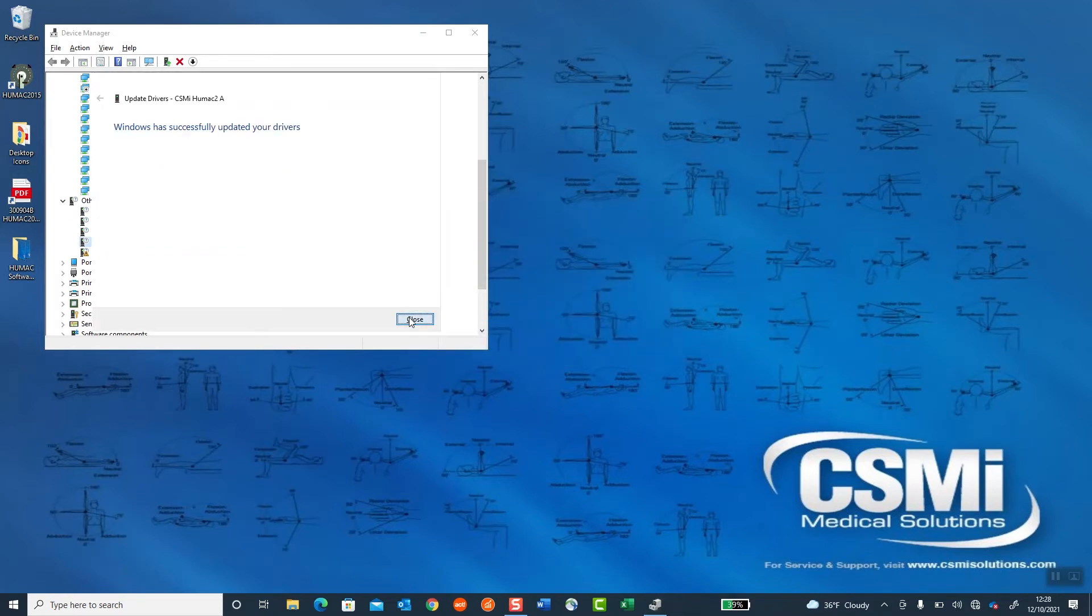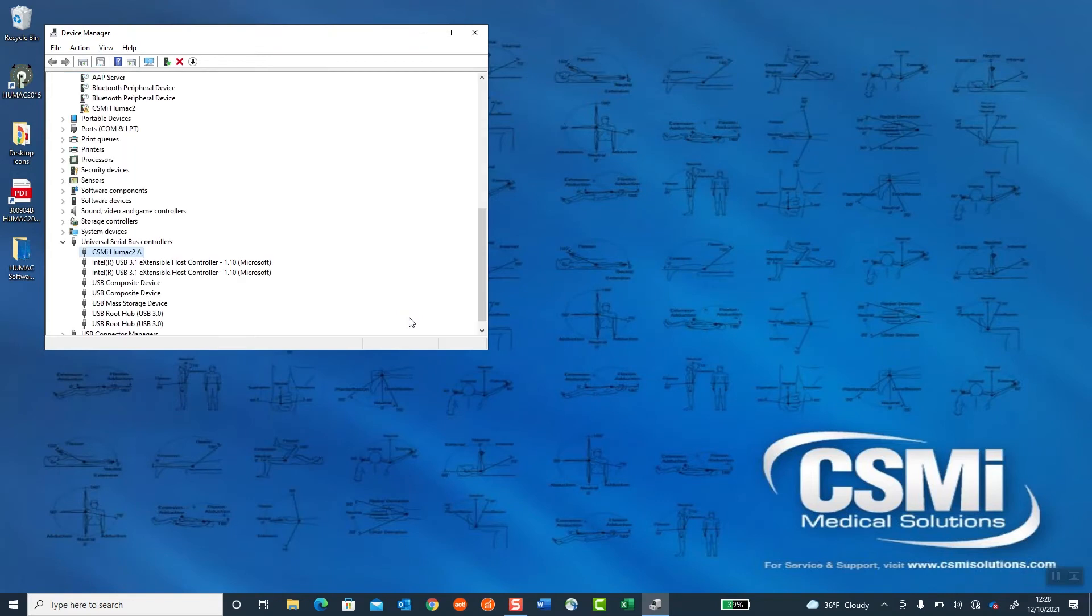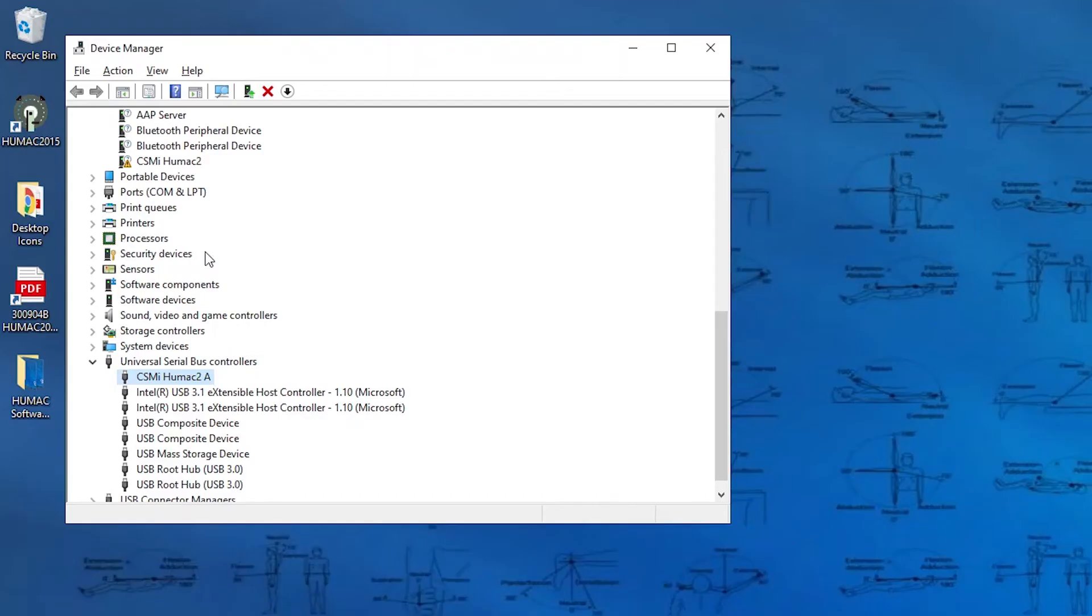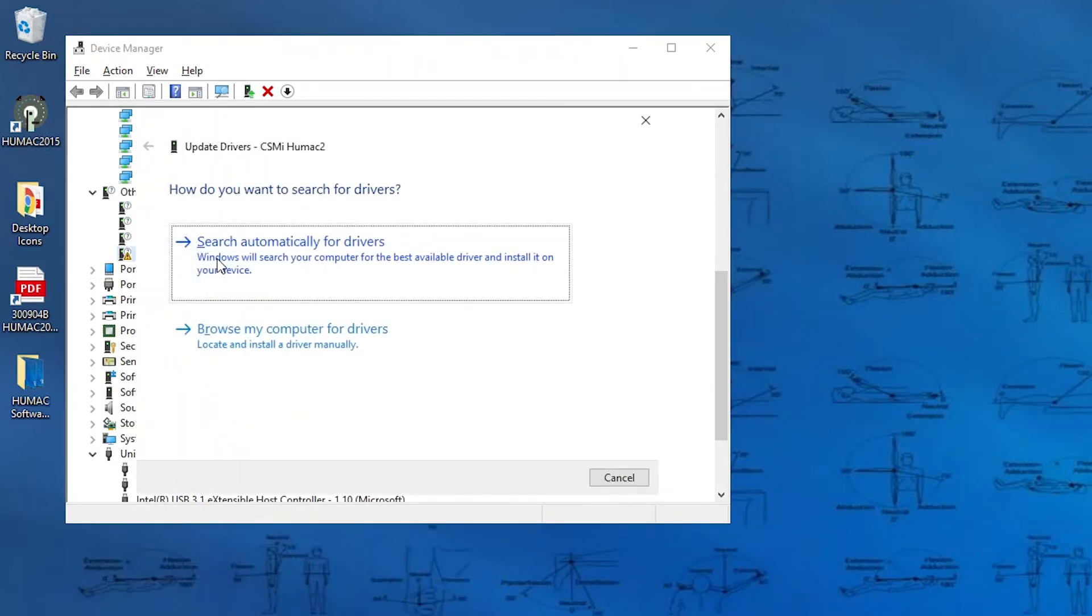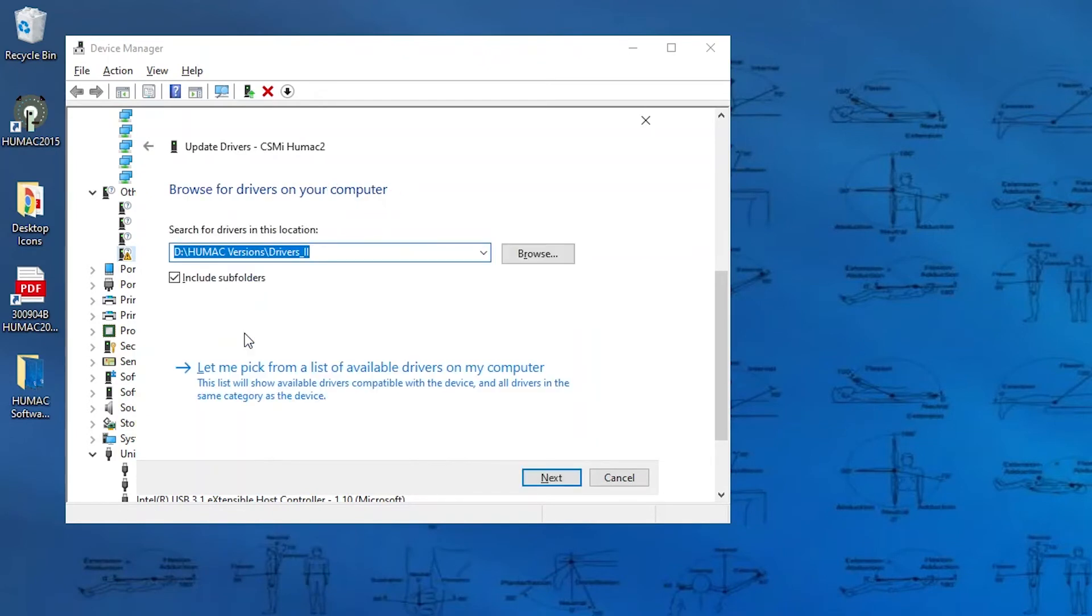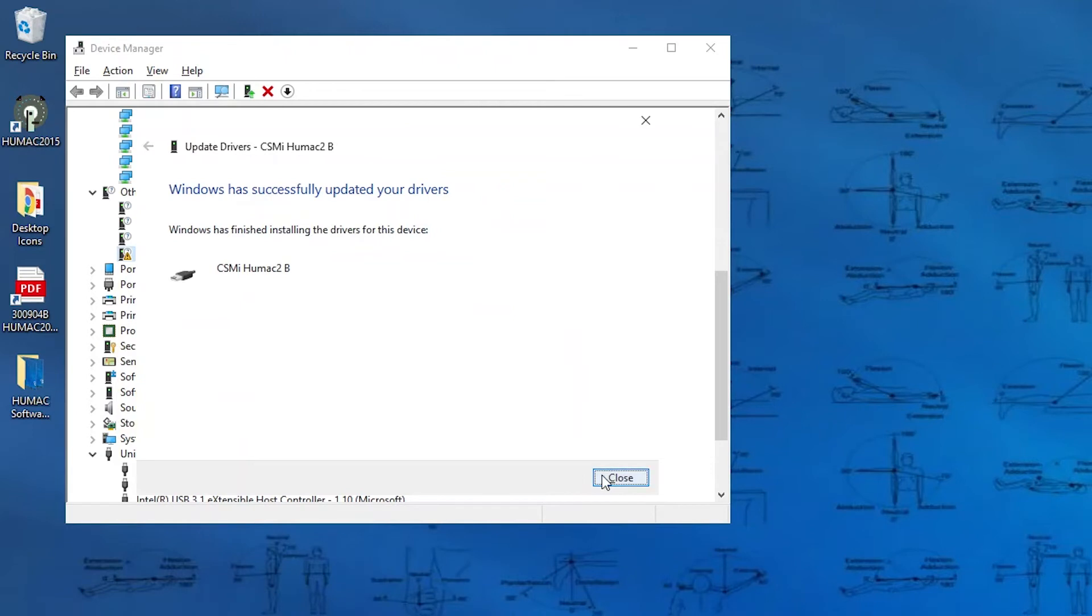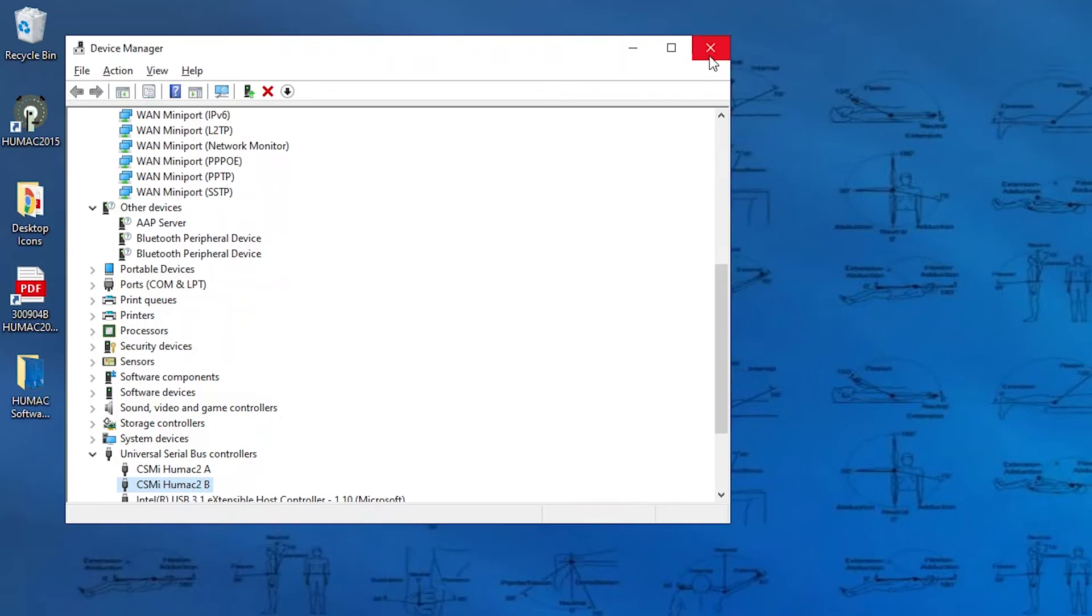Close. Then you need to do the second one, which is under Other Devices up here. Update Driver. Browse my computer. And select Next. Close. And now you'll see the HUMAC ports have moved from Other Devices down to the Universal Serial Bus Controllers, and there are no yellow markers, which means we're good to go.